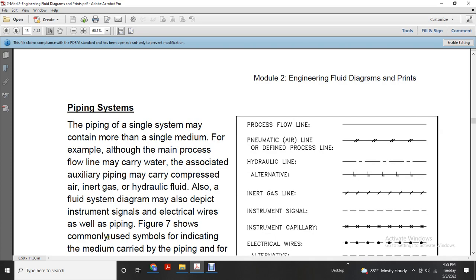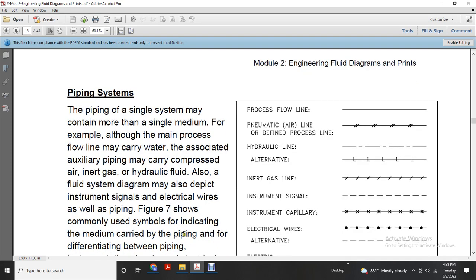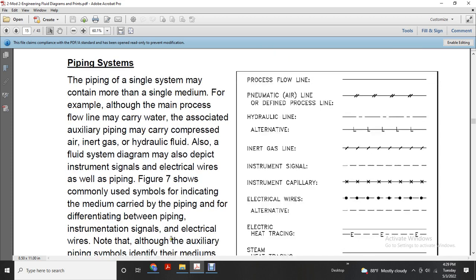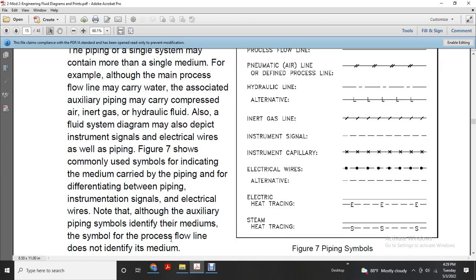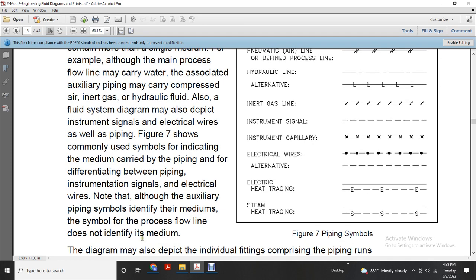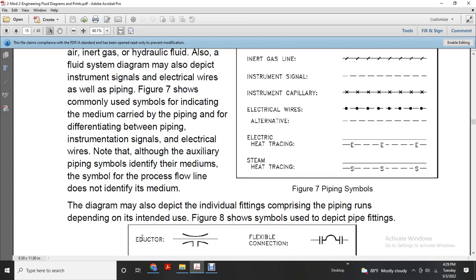Figure 7. Commonly, symbols indicate the medium carried by the piping for the differential between the piping and the instrument signal with the electrical wire. Note that although the electrical and auxiliary piping systems are identified with the medium symbol, the process flow line does not identify the medium. The diagram may also depict individual fittings within the piping run depending on the intended use. Figure 8 shows the symbols that depict the pipe fittings.